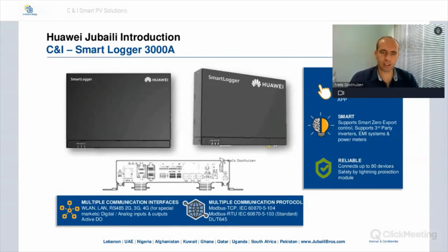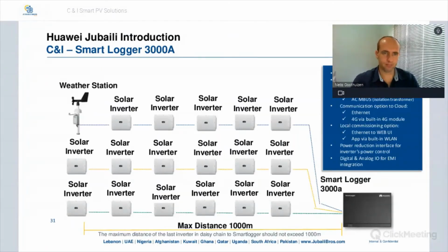So in total 80. You've got about 3 RS485 communication ports on the bottom side. Each port supports a maximum of 30 devices. But just bear in mind that between the 3 ports, all 3 of them cannot exceed 80. This below here is an example of using the Smart Logger 3000A on the RS485. You can go up to a maximum distance of 1000 meters.